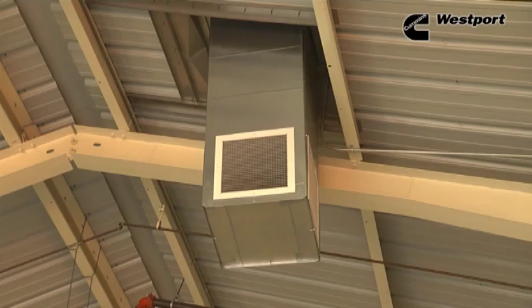I think the roof design is probably the most important element in determining where we position the equipment and how much equipment is installed. The roof design involves looking at how many lights you have and what type—whether they're explosion-proof lights. If they're non-explosion-proof lights, we can still work with that by cutting off the power at 10% of LEL.